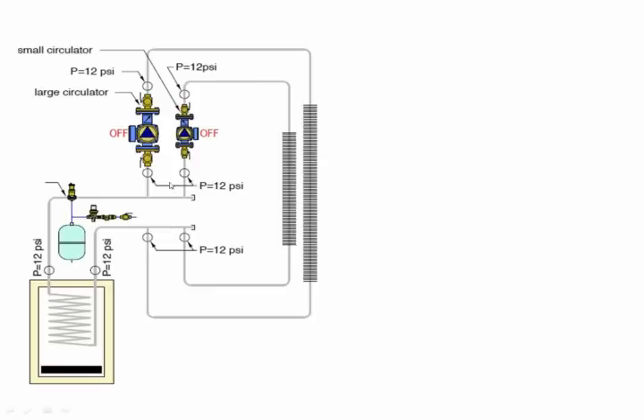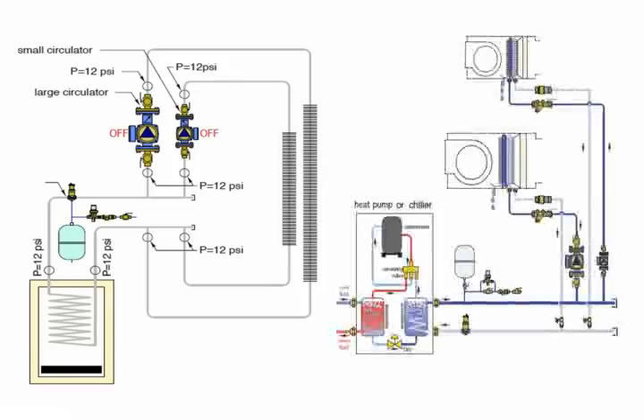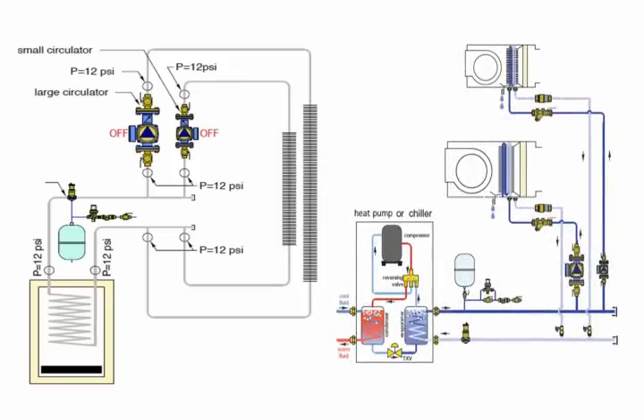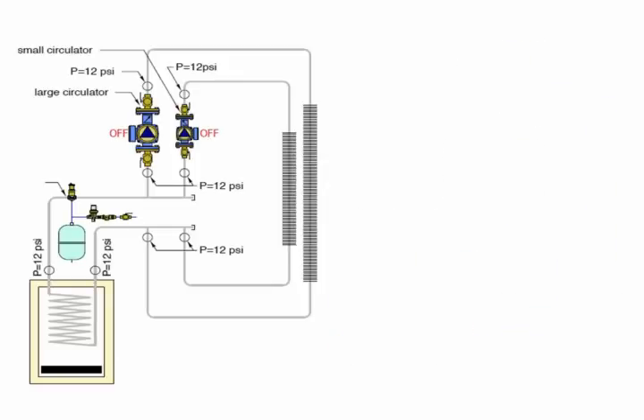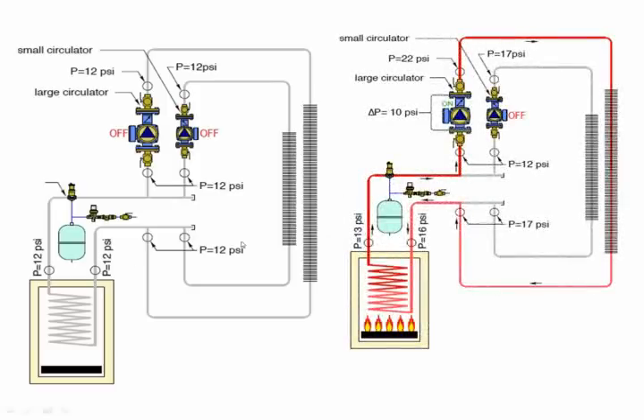So everything is 12 psi. We're going to demonstrate the effect of back pressure, what causes pump conflict, and use some values here. There's going to be a call for heat on this big pump driving heat in this zone over here. It's a 2-zone system, okay? We're going to find out what happens. So take a look at what changes as far as the pressure in our system. Everything's 12 psi to start off with. Now, this is a heating system. We could have been talking about a chilled water system. The mechanics are exactly the same. So we'll stay with heating.